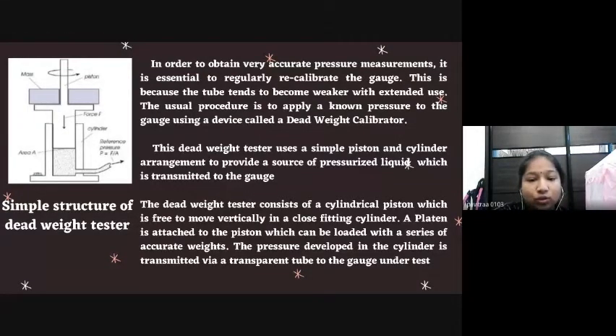This figure shows the simplest structure of a deadweight tester. In order to obtain very accurate pressure measurements, it is essential to regularly recalibrate the gauge. This is because the tube tends to become weaker with extended use. The usual procedure is to apply a known pressure to the gauge using a device called a dead weight calibrator. The normal calibration procedure is to load the gauge with known pressures using a dead weight calibrator including a liquid of known specific gravity, which is water here. This dead weight tester uses a simple piston and cylinder arrangement to provide a source of pressurized liquid, which is all transmitted to the gauge.